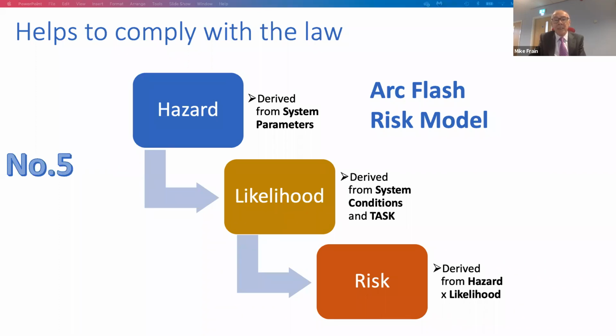The cornerstone of risk assessment means that any employer must evaluate all the risks to the safety and health of workers. Arc flash risk assessments for workers who operate in the proximity of energized equipment, cables and overhead lines are an essential part of electrical safety management. Calculations give us the means to evaluate the hazard and also the means to provide prevention techniques such as automatic disconnection of supply for arcing faults.